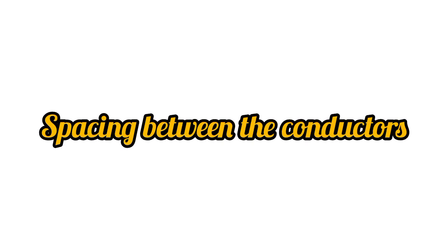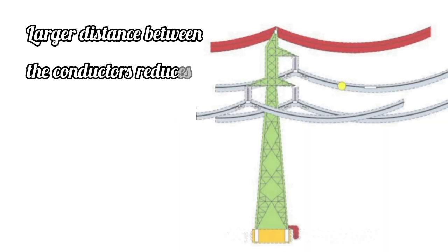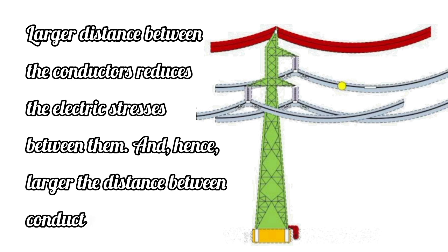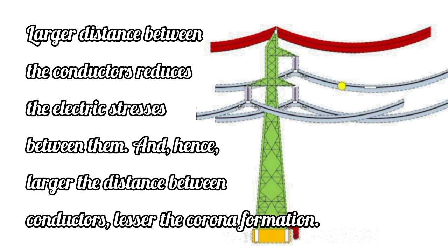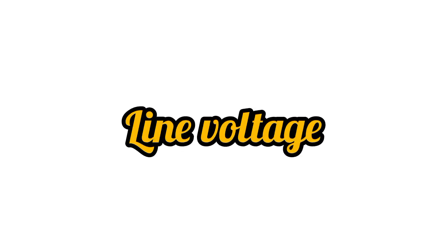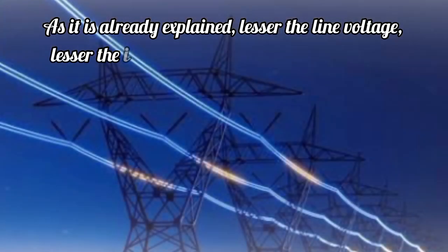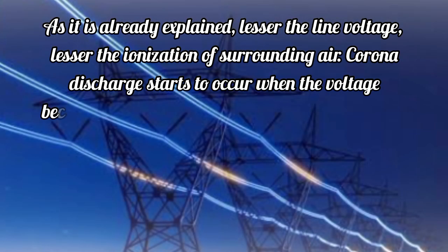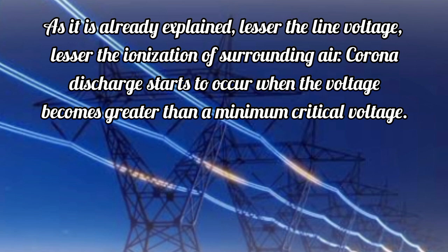Spacing between the conductors. Larger distance between the conductors reduces the electric stresses between them. And hence, the larger the distance between conductors, the lesser the corona formation. Line voltage. As already explained, the lesser the line voltage, the lesser the ionization of surrounding air. Corona discharge starts to occur when the voltage becomes greater than a minimum critical voltage.